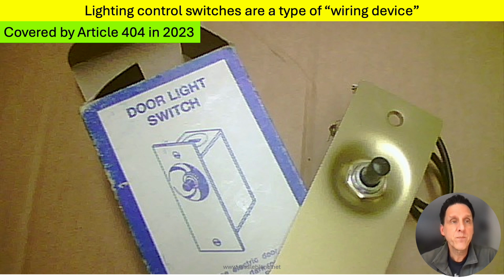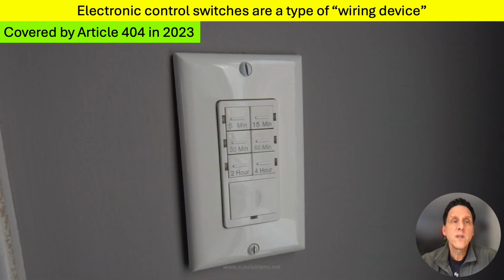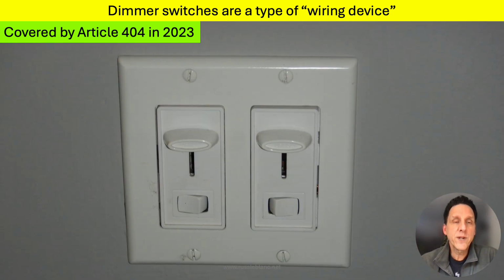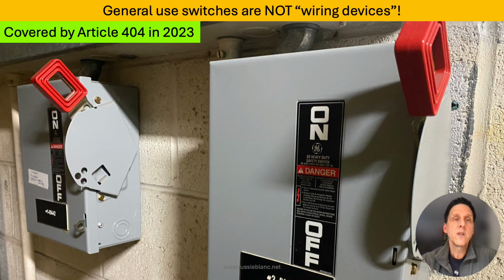It was covered by Article 404. Electronic control switches like this timer are, again, another example of a wiring device covered by 404 in the 2023 code. Dimmer switches like these slide type dimmers, covered by 404 in 2023. Now, general use switches, right? These are not snap switches, but they're general use switches. These are covered by 404 in the 2023 code.